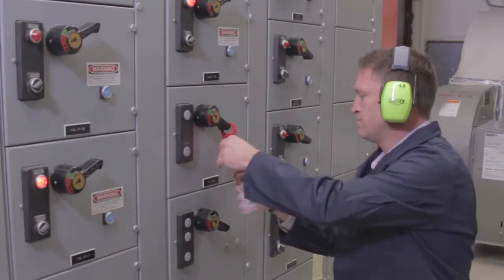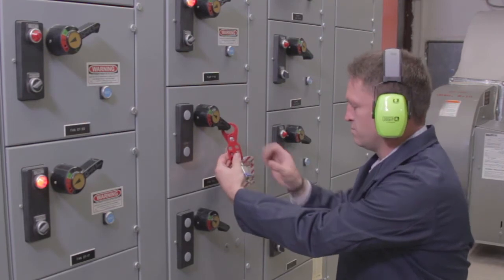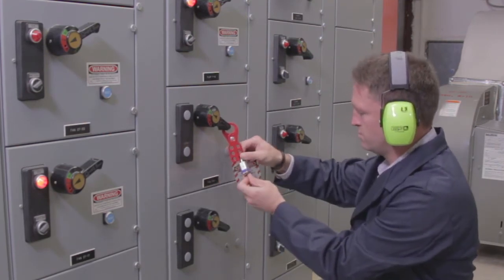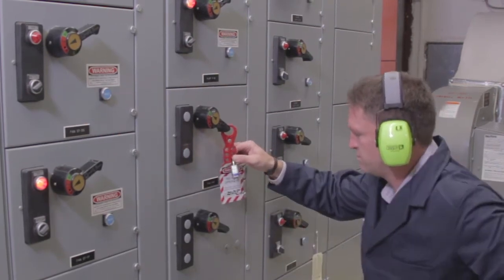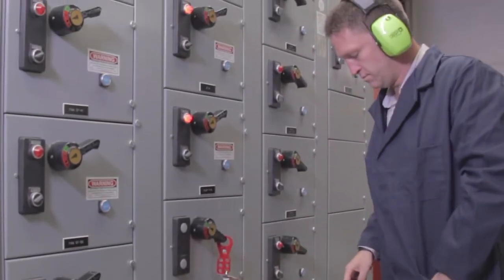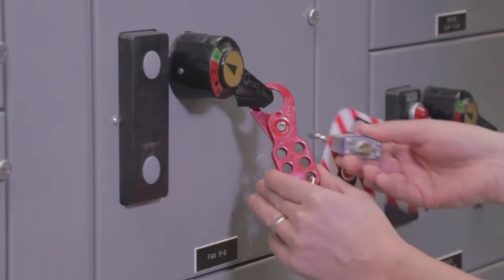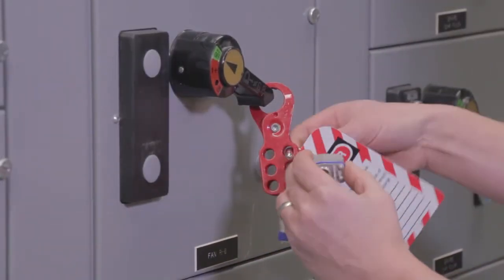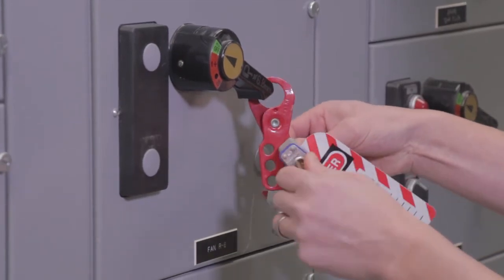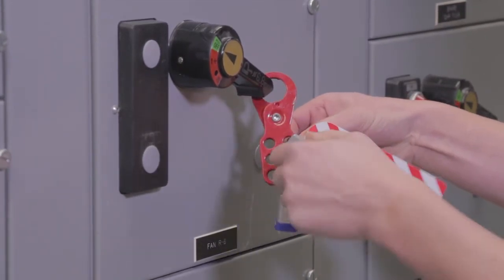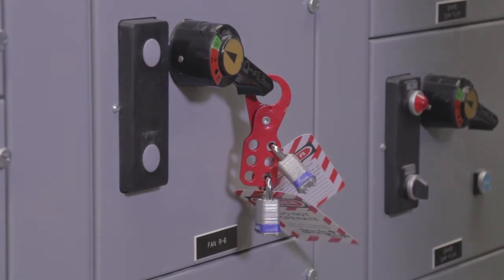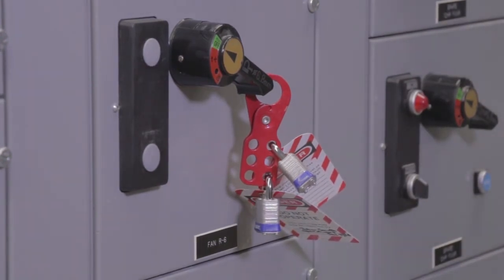During the time of your lockout service, you may finish your shift or be called to leave. If the lockout is continuing until you return the next day, you would keep the key. If someone else needs to be involved or complete the lockout, you must make sure that they've applied their own board-approved lockout device on the same hasp as yours before removing your device. Never give your key to anyone, including a fellow caretaker or maintenance staff member.